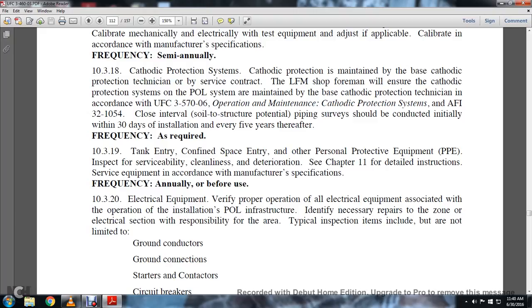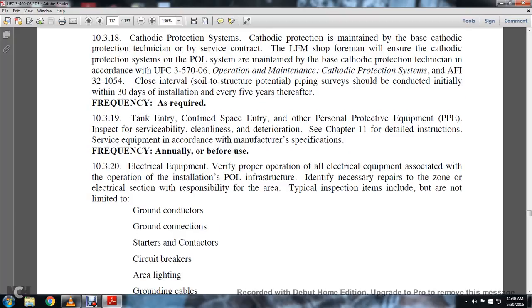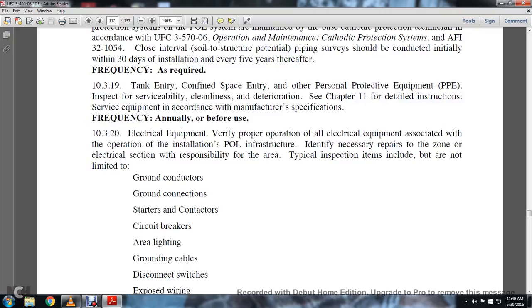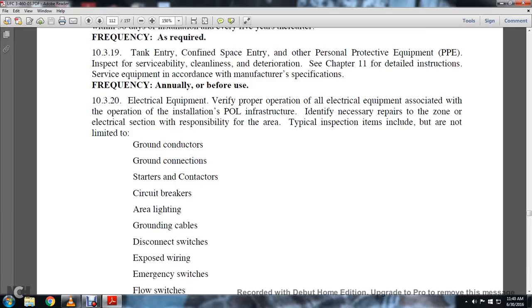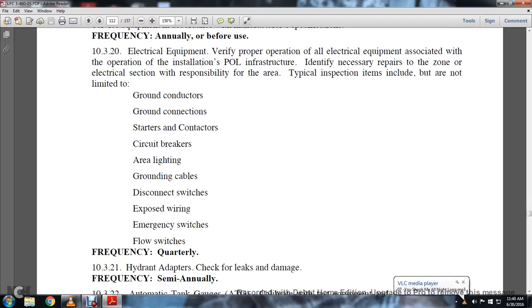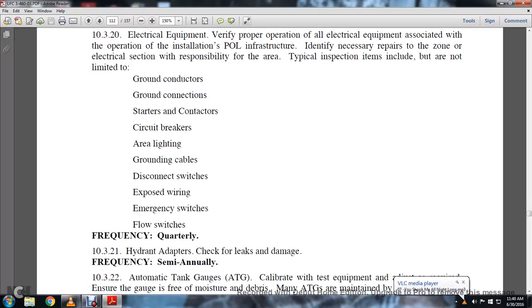10-3-20 Electrical equipment. Verify the proper operation of electrical equipment associated with the operation and installation of the POL infrastructure. Identify necessary repairs to the electrical section responsible for the area. Typical inspection items include, but are not limited to, ground connectors, ground conductors, ground connections, starter contactors, circuit breakers, area lighting, ground cabling, disconnect switches, exposed wiring, emergency switches and flow switches. Frequency: check the electrical equipment quarterly.